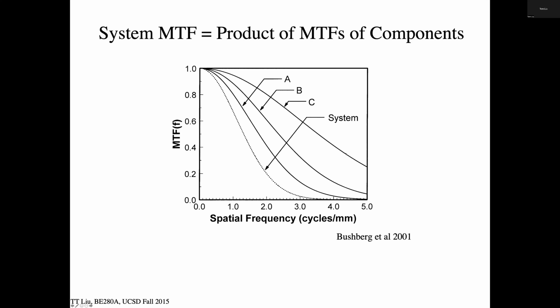And if they're trying to tell you that their system can image very fine structure, not only will they show you clinical images of, say, the inner ear, where you see these extraordinarily fine structures like that little stirrup thing, these tiny structures are well resolved. So they'll show you that. But then they'll show you the modulation transfer function.